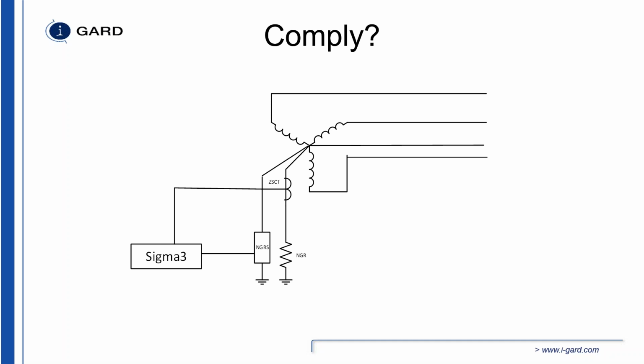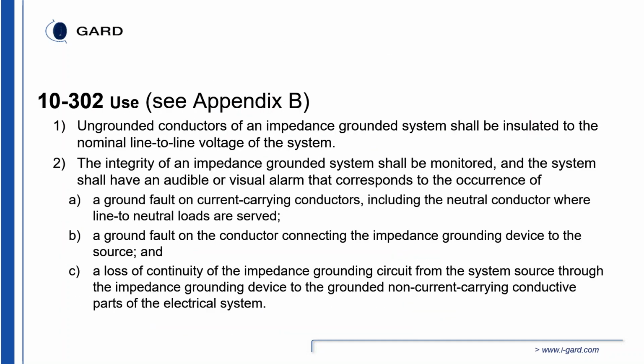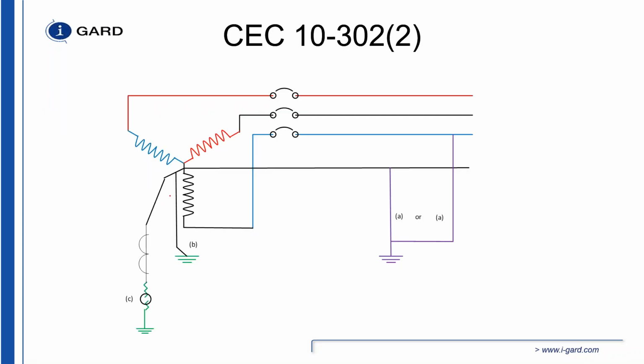This person's wondering how you comply with CEC 2018 with a reactor grounded system. Is passive mode detection sufficient? No, I would say that using a reactor with the current way that the code is written will not work, because you cannot detect an open circuit, or basically you can't detect this.